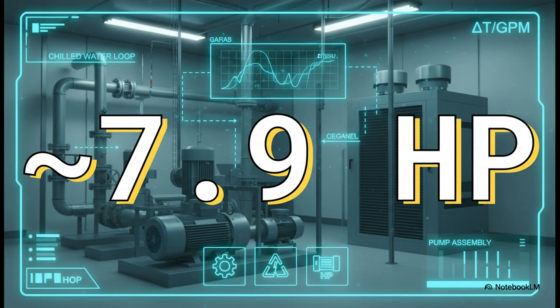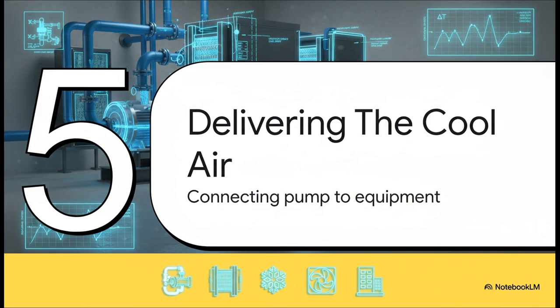So you run the numbers through the formula, and it comes out to about 7.9 horsepower. Now here's the thing, you can't just go out and buy a 7.9 horsepower motor. So what an engineer does is they look at this and select the next standard motor size up, which in this case would almost certainly be a 10 horsepower motor. All right, so we've sized our pump, it's ready to go. Its job now is to deliver that precise flow of chilled water to the equipment that's actually going to interact with the air that we feel.